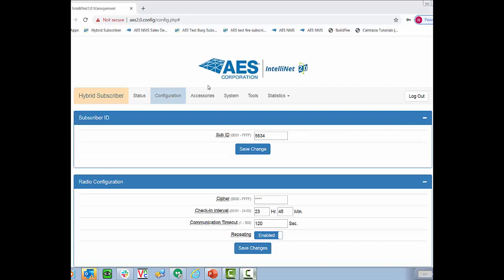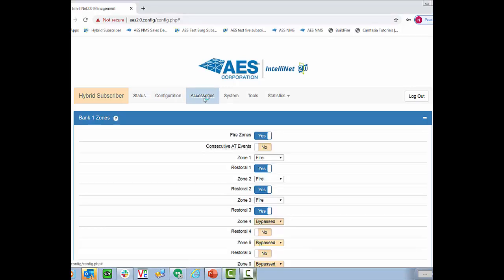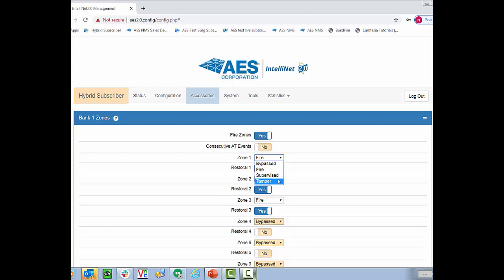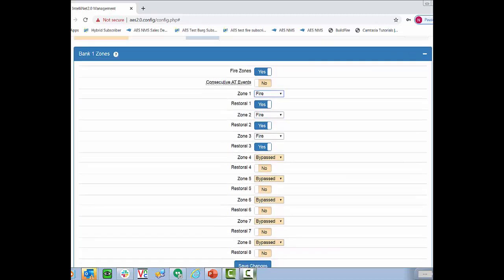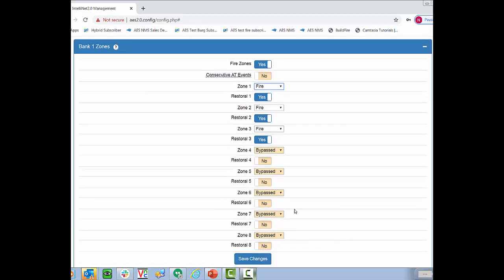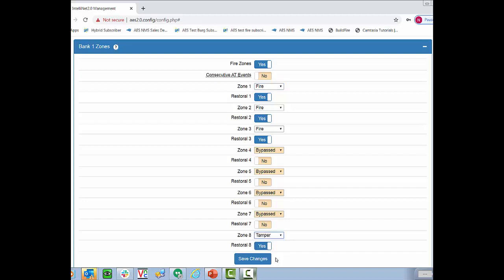what we're going to do is figure out how we want to connect the subscriber to the fire alarm panel. Under the accessories tab, we'll see we can program the dry contact zones. There are four options for each of the eight zones. Fire, supervised, tamper, and bypassed. Be careful using the supervised as this sends an alarm on open and an alarm on short. We find most people generally, if they're using the dry contacts, will use zone 1, 2, and 3, and then zone 8 for a tamper.